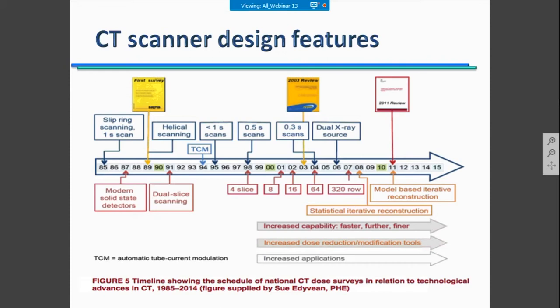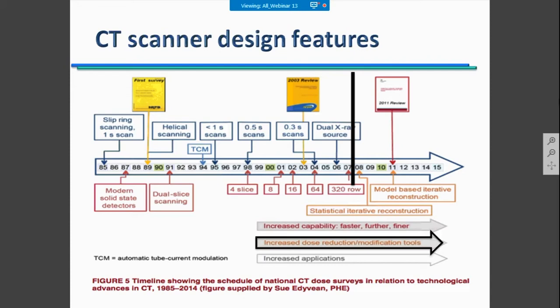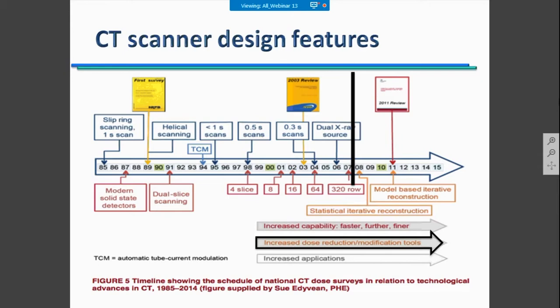It's important to know how to use your CT scanner to promote optimization. CT scanner design features have changed over the years. In the last decade, scanners were designed to increase capacity, be faster, and get finer image details. However, recently, they are also providing tools to reduce dose while maintaining image quality. Independently of the type of scanner you have, you could use different optimization tools that are available in all scanners.